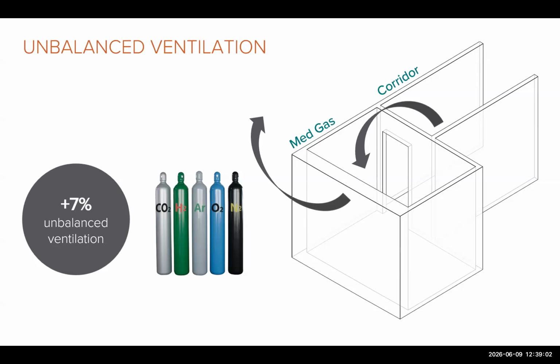Using the ERV for intake air but not exhaust air is causing the ERV to be unbalanced at 7%. That's just the ERV that's serving this area. So the building as a whole is positively balanced to within 1 to 2%. That's under the Phius limit of 10%. We're feeling pretty good about it, but we're going to have to watch it during construction.